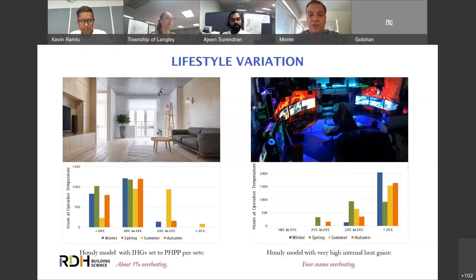But next door, say a couple lives in a 2-bedroom apartment and they both love gaming. They've used their second bedroom for 5 or 6 CPUs, screens, and lighting, spending 8 hours a day on these computers as entertainment. This isn't tremendously uncommon. It's quite possible they're producing 500 to 1,000 watts of real-time heat in that bedroom, more than enough to heat their apartment and 2 or 3 apartments along the hall. They'll have a worse overheating problem, and their neighbor on the other side of that bedroom may have a worse overheating problem than elsewhere. So our variation in internal behavior also affects how much heat gain we have.